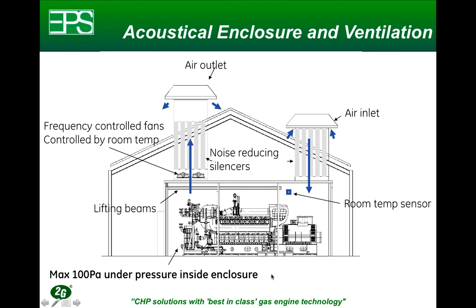This shows how this would work within an indoor installation. You have the enclosure that houses the generator set. You have the air inlet with the silencer. You have variable frequency drive fans to control the temperature inside the enclosure. You have lifting beams over top of the engine to make sure that the heavy components can be easily lifted. And this provides the optimum environment for an engine to operate in.